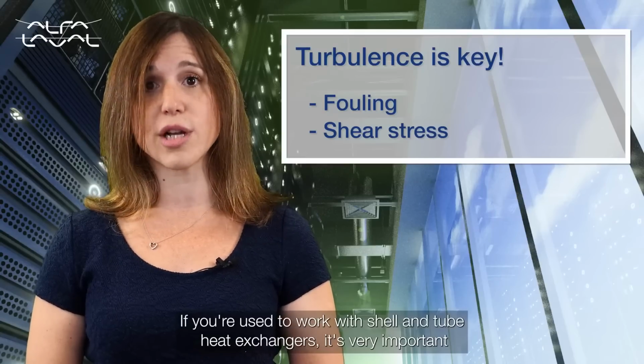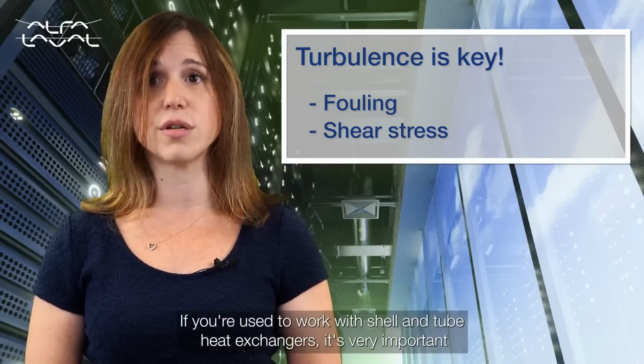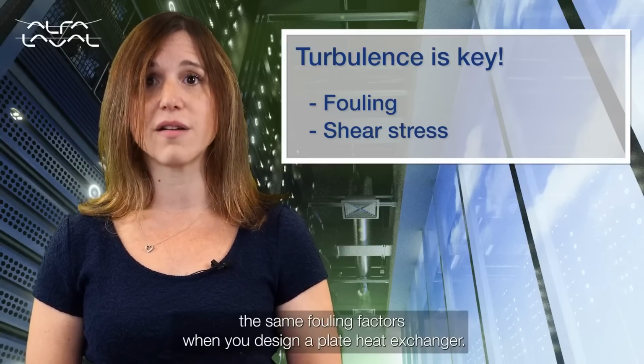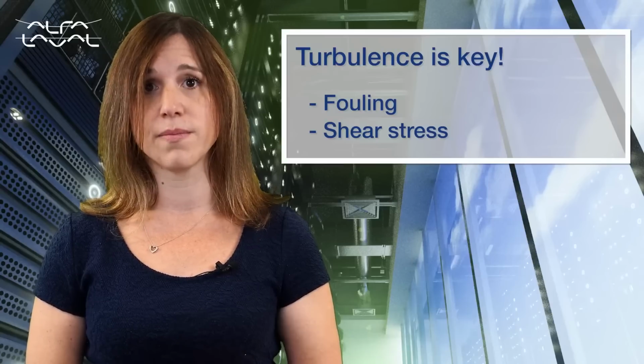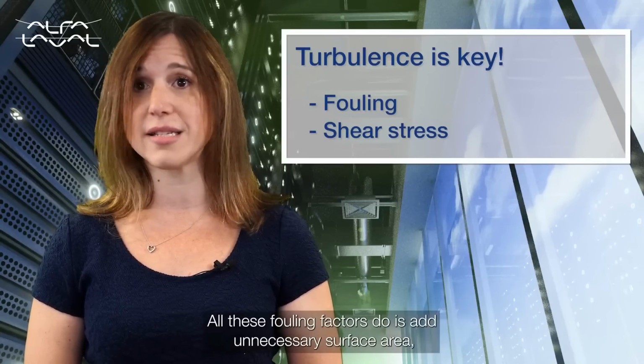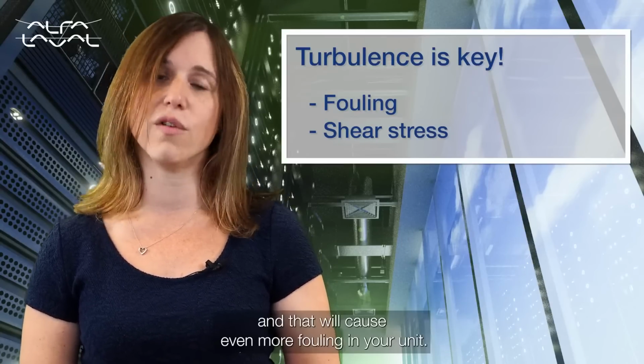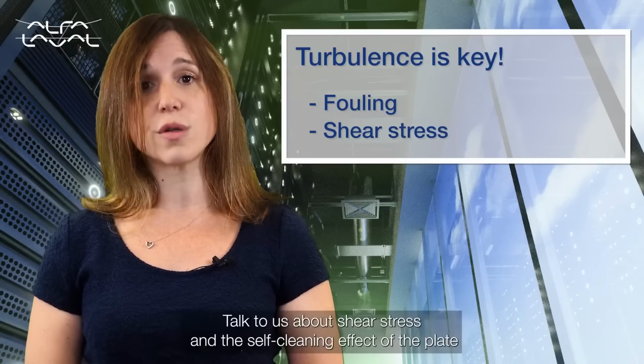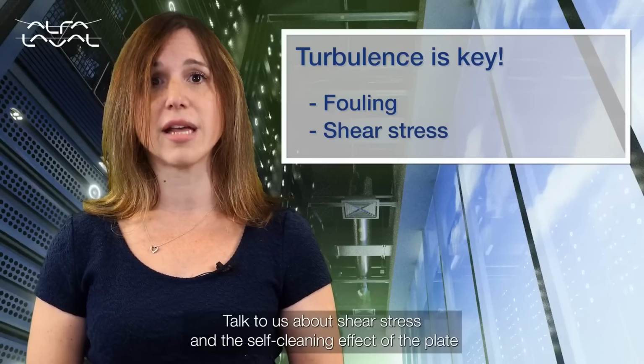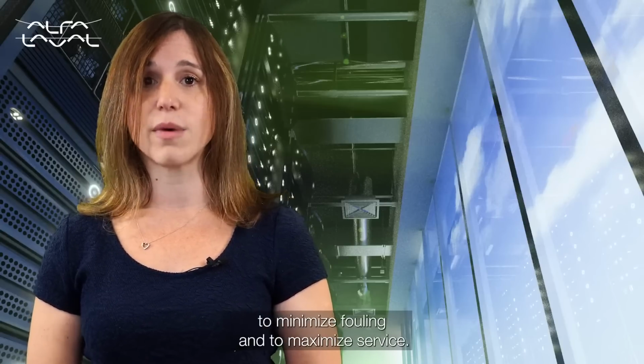If you're used to working with shell and tube heat exchangers, it's very important to know that you cannot apply the same fouling factors when you design a plate heat exchanger. All these fouling factors do is add unnecessary surface area, and that will cause even more fouling in your unit. Talk to us about shear stress and the self-cleaning effect of the plate to minimise fouling and to maximise service.